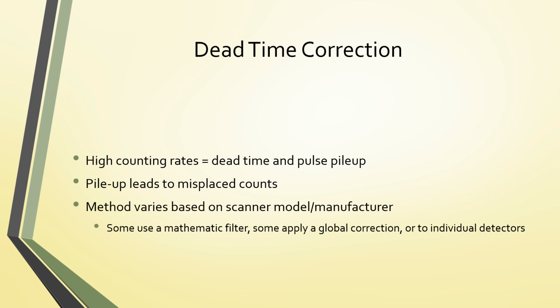So you have really high counting rates with PET, and that leads to dead time and pulse pileup. Pulse pileup will lead to misplaced counts, and of course, dead time will lead to lost counts. So the method varies based on the scanner model and the manufacturer. Some use a mathematic filter, some apply global correction, or to the individual detectors. I also want to point out with the dead time with PET scanners, especially if you're doing cardiac PET, for example, you want to pay really close attention to the count rate that you're getting and the ability of the camera to process those. Sometimes you may need to reduce the dose to the patient in order to avoid dead time. Some scanners are just a lot more sensitive than others, so they're a little more susceptible to dead time.